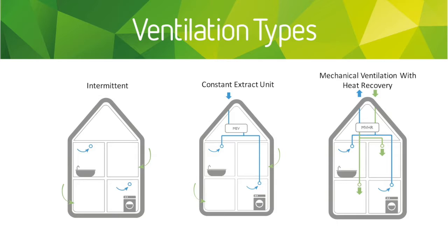And that's probably one of the main reasons why studies show that these systems do not work. I appreciate that building regulations allow this to happen, because in theory you use trickle vents and you use the windows, but in reality people don't use them properly, and people will sit in a room that has a very high CO2 level, but you won't realise that you are sitting in there unless you have indoor air quality sensors, which pretty much no new homes have, unless you specify one.